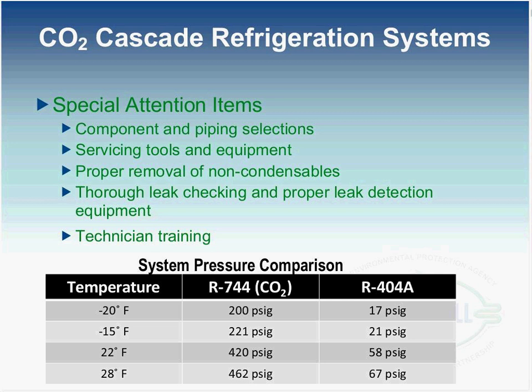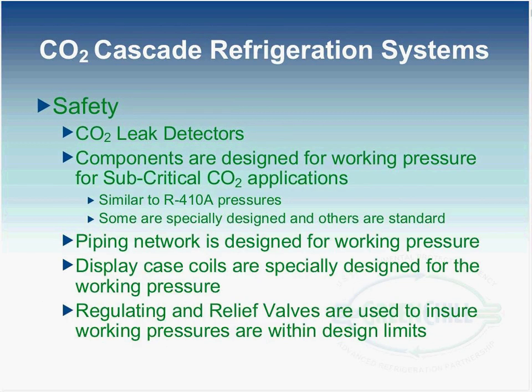I do want to mention, I alluded to this a little bit earlier, but there is a very significant difference in operating pressures going from a standard HFC refrigerant like R404 up to a CO2 type refrigerant. Looking at a factor of anywhere from about, I believe, 7 to 13 times, going from about 17 PSIG to about 200 PSIG. So you definitely have to take considerations into your piping and components there. I want to reinforce that really quickly. And also I want to touch, of course, on safety.